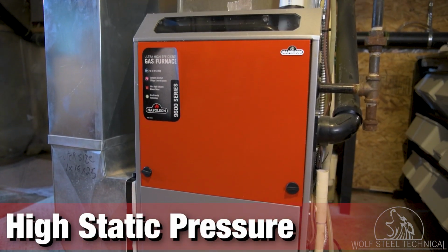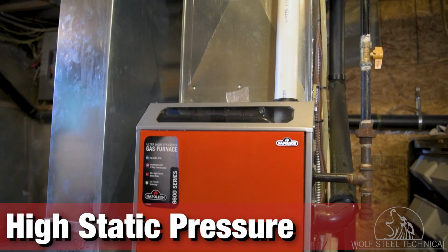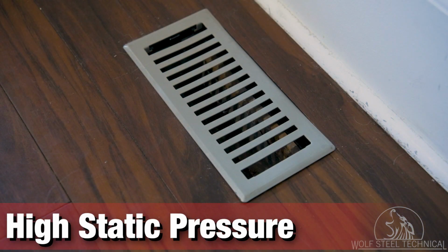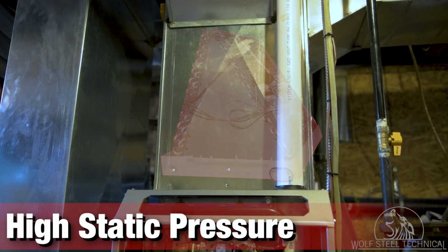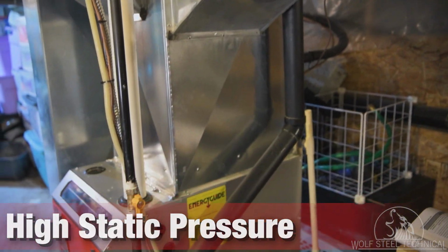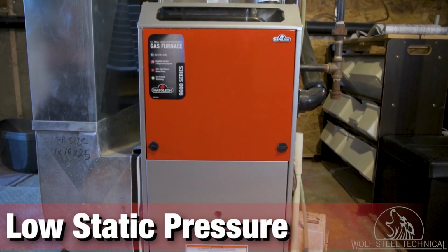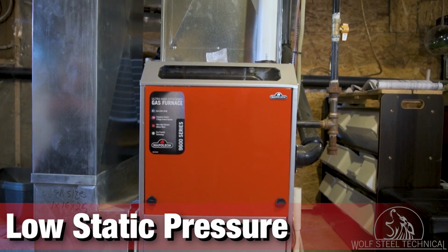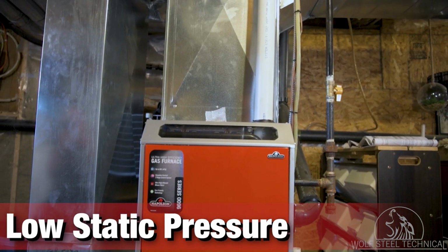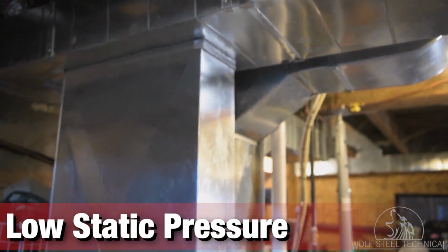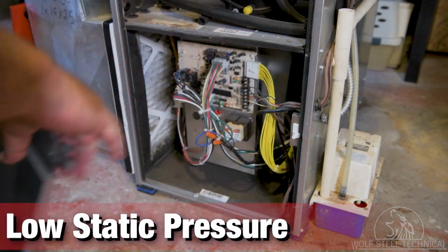If the static pressure measurement is too high, it may indicate that there is a problem such as a clogged air filter, closed damper, dirty or clogged A-coil, or blocked or undersized ductwork. If the static pressure measurement is too low, it may indicate that there is a problem with the HVAC system, such as oversized or leaking ductwork, or an issue with the blower fan.